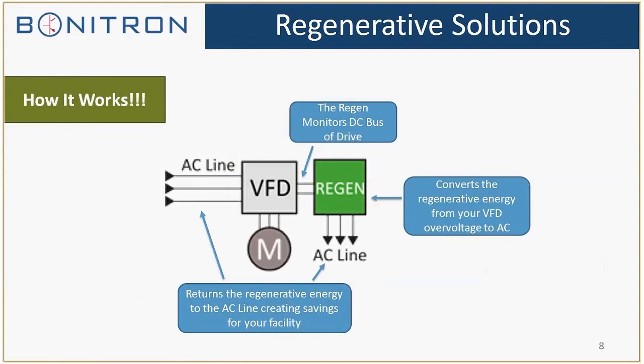Now let's get into how it works. The regen is going to monitor the DC bus of the drive, then convert the regenerative energy from your VFD overvoltage occurrence to AC. These are IGBT-based modules — not transistor SCR, they are IGBT-based. From the regen module, you're going to return the regenerative energy back to the AC line of the facility.